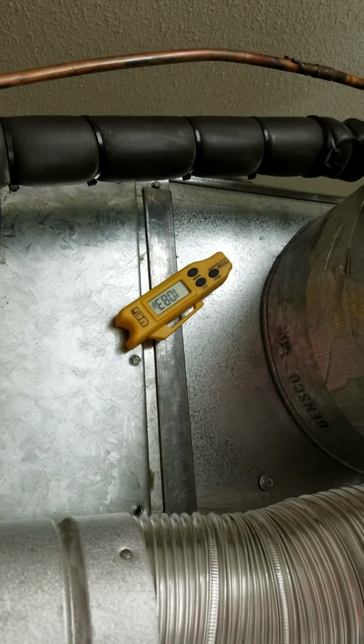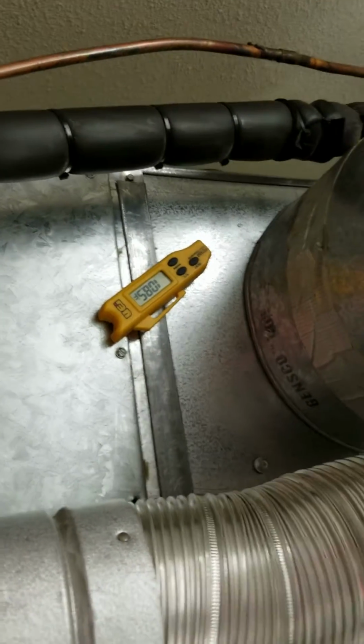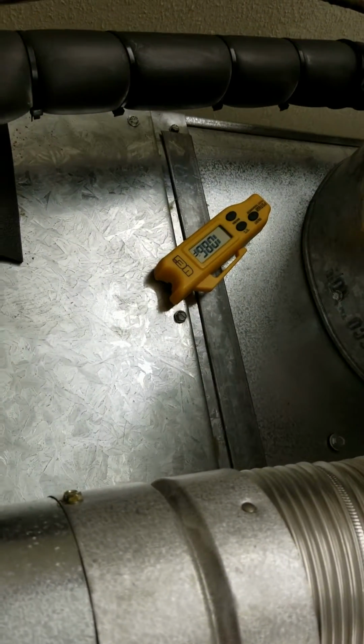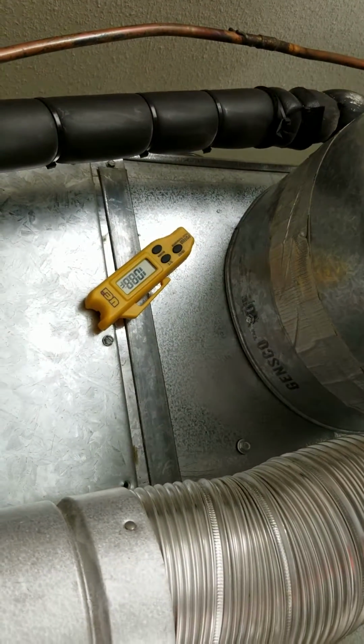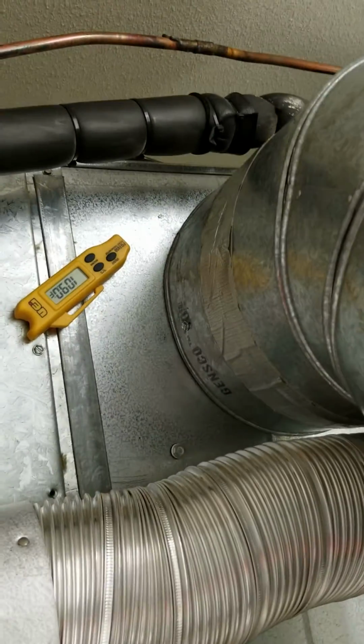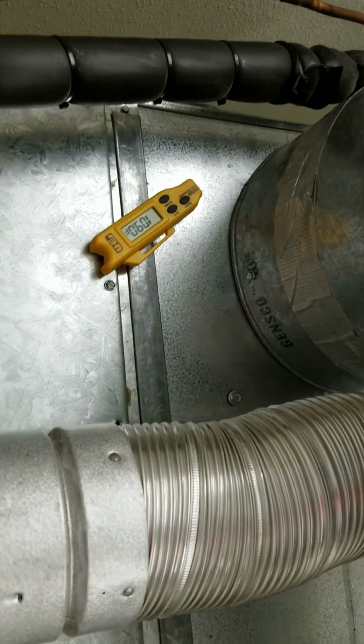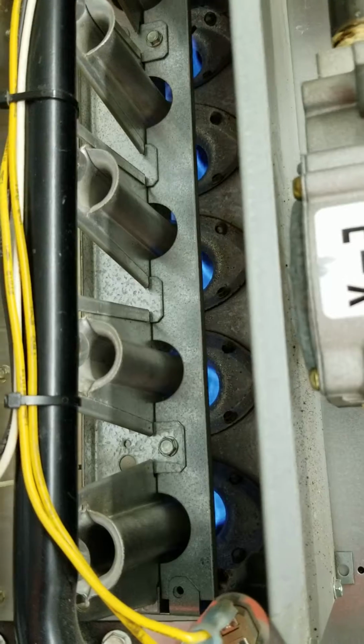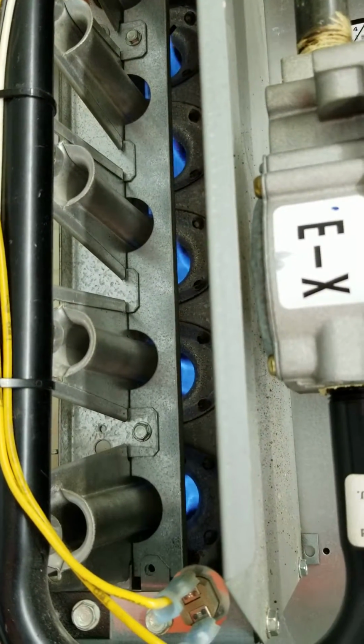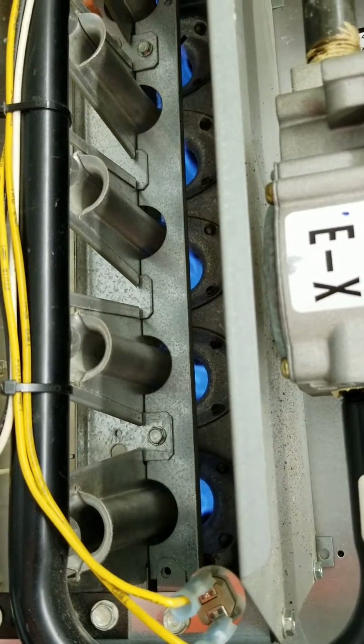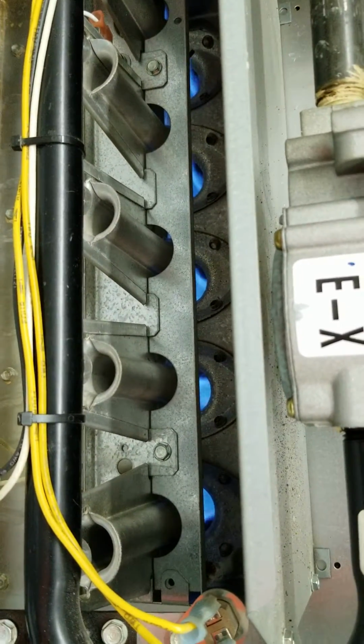It's going to take a little while to get there, but otherwise this furnace appears to be in good working order. So, Damien, if you want to go ahead and shut the thermostats down right quick, one last thing we will do to this. Actually, two last things. And when the thermostats are satisfied, the next thing that happens, but we simulated this by turning them down. And we're waiting for the burner to shut off.